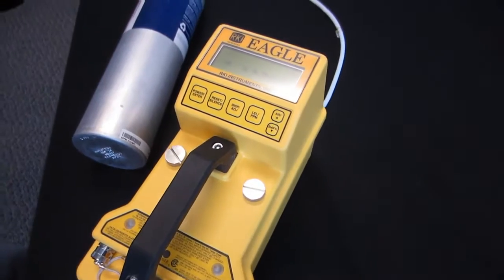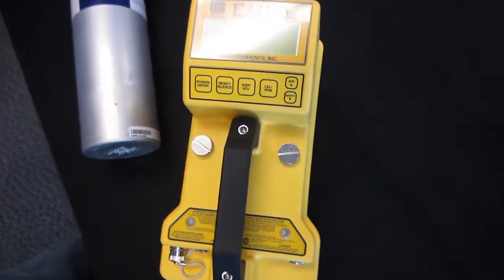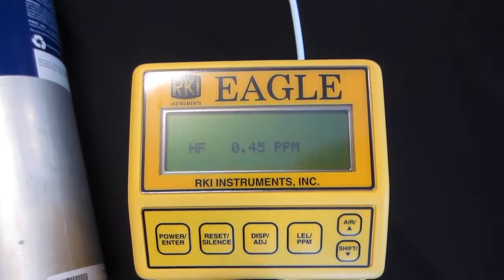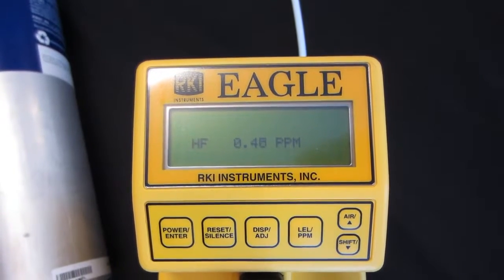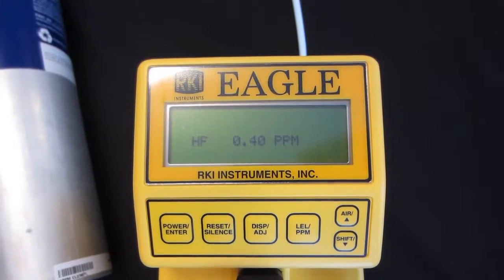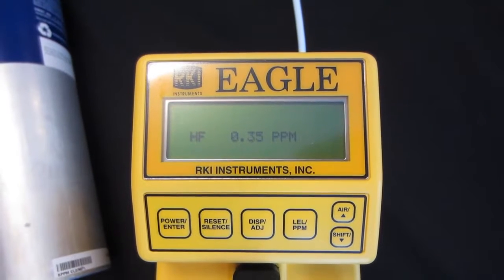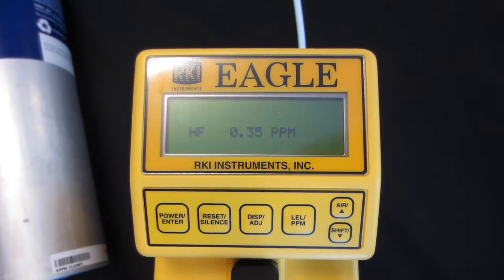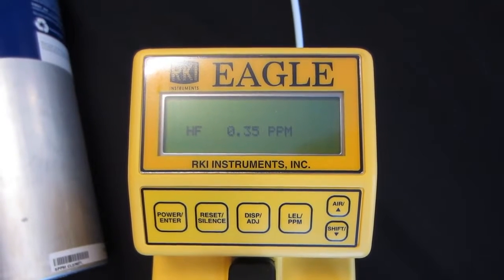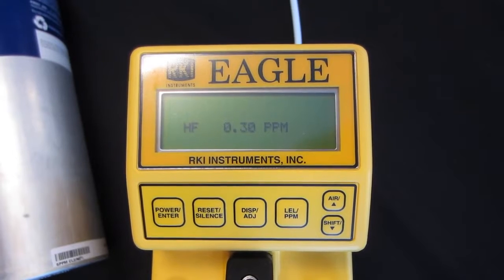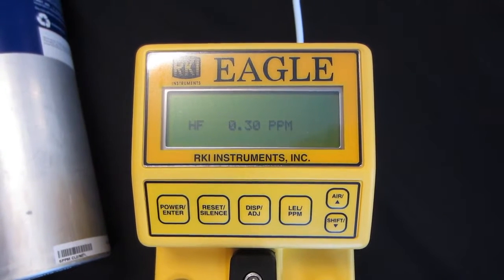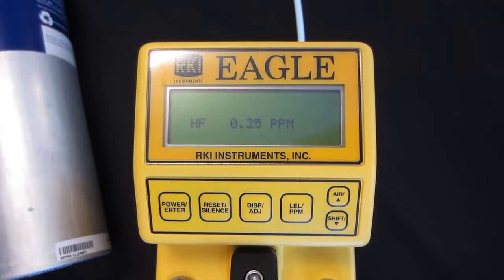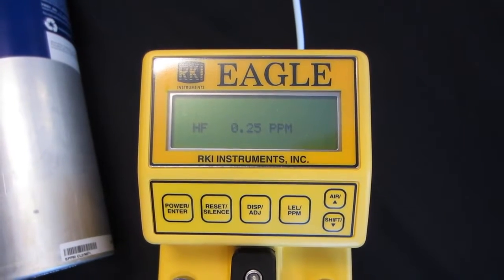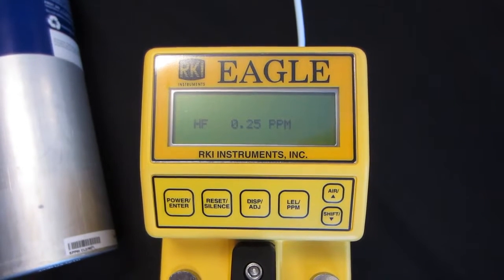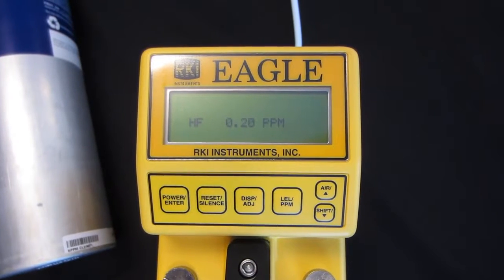Okay. And the reading will continue to drop towards 0, and it may take a few minutes before it clears out of the flow system. So you may want to conduct bump tests just by looking to see that the alarms are tripped. Some people do that. They just apply the gas long enough to make sure it reaches the alarm points and trips them. Other people like to see how close it gets to the cal value. It might be a value of plus or minus 30% of the cal value, or 20%, or 15%, something of that nature. Usually 20 to 30% is a good quick value to arrive at, so that you can do your bump tests quickly.